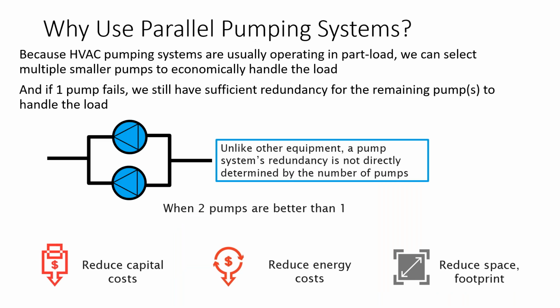So why do we use a parallel pumping system? HVAC pumps are usually operating at part load, so we can select multiple smaller pumps to handle that load. And if one pump fails, we'll still have sufficient redundancy from the remaining pumps to handle that load. Unlike other equipment, a pump system's redundancy is not directly determined by the number of pumps. So we can reduce capital cost, reduce the energy cost, and reduce the physical footprint in the space.